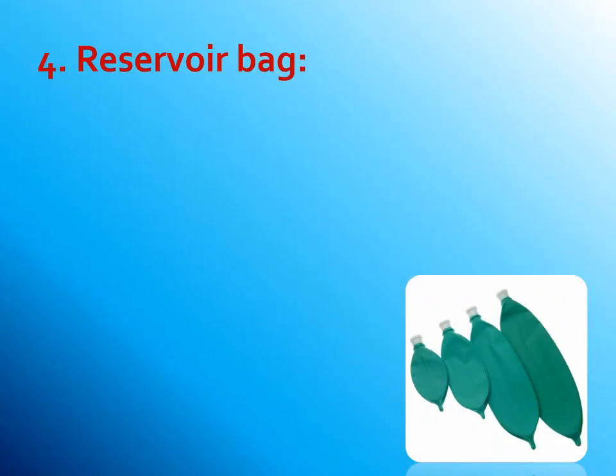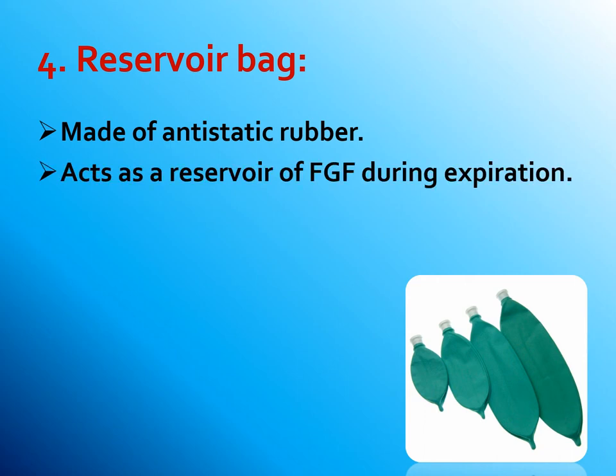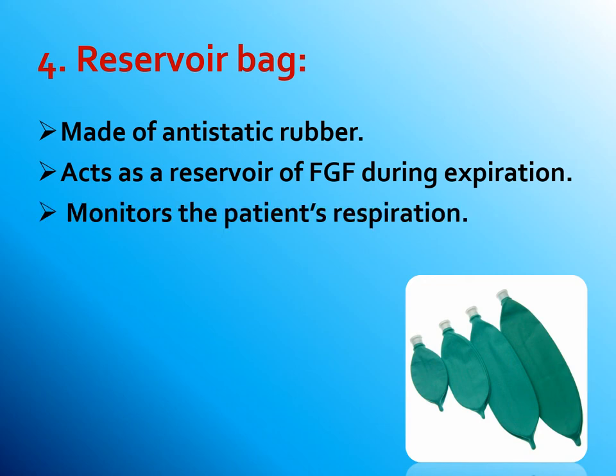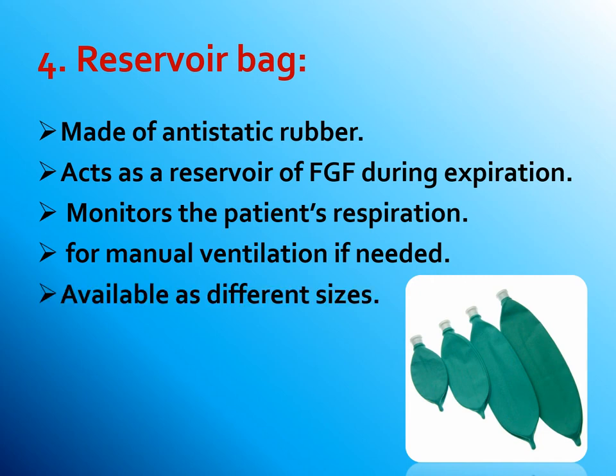The fourth component is the reservoir bag. Made of anti-static rubber, it acts as a reservoir for fresh gas flow during expiration, monitors the patient's respiration for manual ventilation if needed, and is available in different sizes.